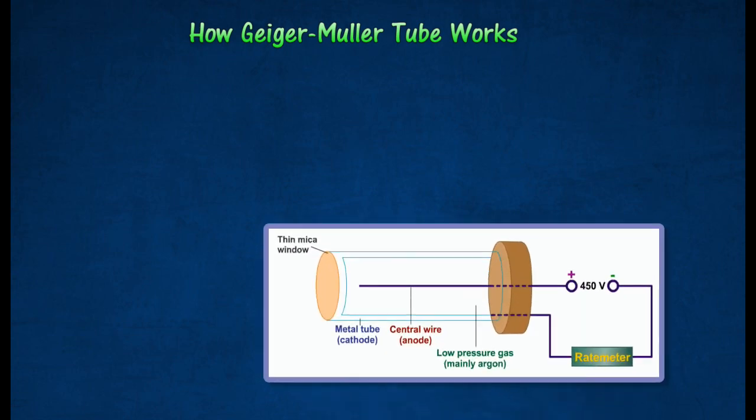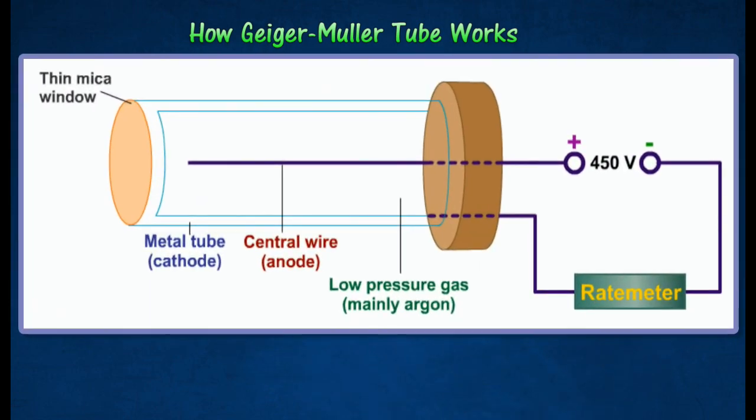The Geiger-Müller tube has two electrodes across which a voltage of about 400 volts is applied. A central wire acts as the anode, while the cylindrical metal wall of the tube forms the cathode.